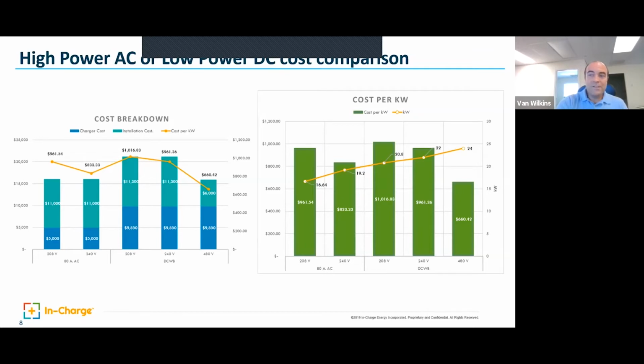As you move into a DC charger, a small DC charger like a 24 kW, you can charge faster, but there's a little more cost to it on a smaller service, because if it's 208, you've got to put in a larger wire, larger pipe. So the cost is higher on a DC charger on a small commercial service. If you move into a building that has 480 volt power, now because I can use smaller wire, smaller conduit, it's a lot cheaper to put in the DC charger there. It's still price-wise, it gets down to about, it's going to be pretty comparable, equal to a high power AC on a commercial building versus low power DC.